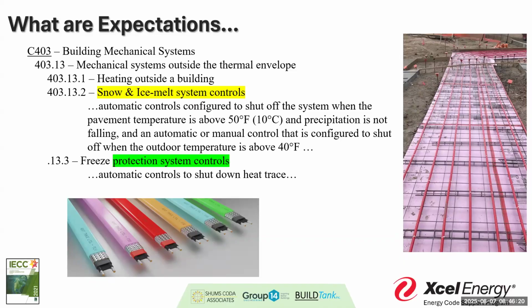If it gets super cold and you're running water, even if you're running that water, it's going to freeze, it's going to buckle, it's going to bust. So we want to make sure we think about those, whether it's snow melt or cold dampening. Make sure we think about those systems, and then what kind of other things we're doing to protect the building, how we're tracking and where that sensor is. Again, it gives my inspector the ability to go out and verify that: where's that sensor? Oh yeah, so that's what that is. There's your sensor telling you the outdoor temperature to shut off that heat trace tape or that snow melt system.